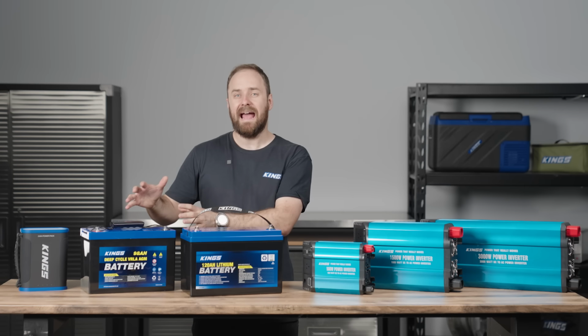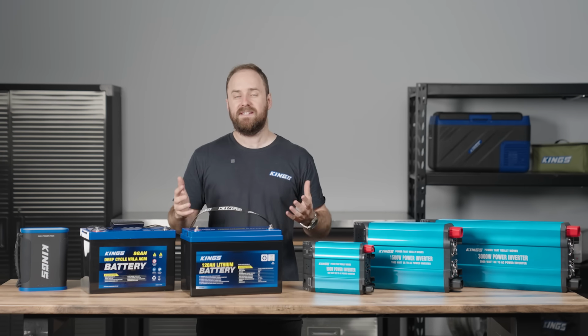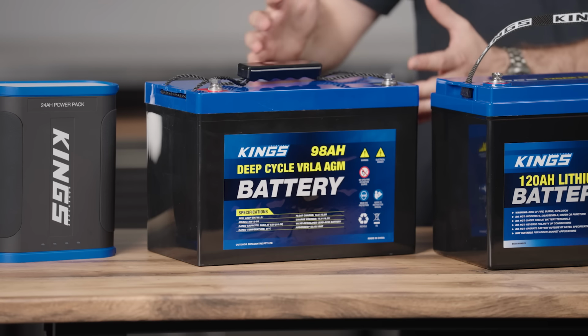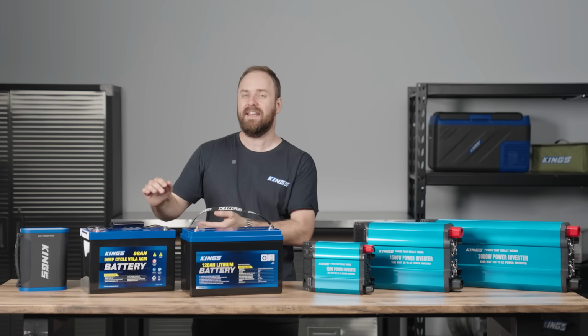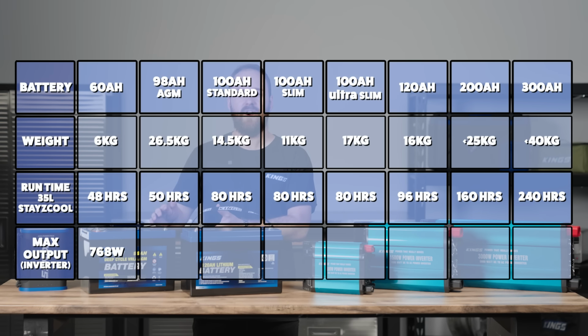Next up, we will add the 98 amp hour AGM into the comparison. AGM batteries don't have a BMS and they have a lower nominal voltage, so we don't really recommend them for running inverters. If you did try and run a 1500 watt inverter on this battery, it would be down to about 50% remaining in around 10 minutes.